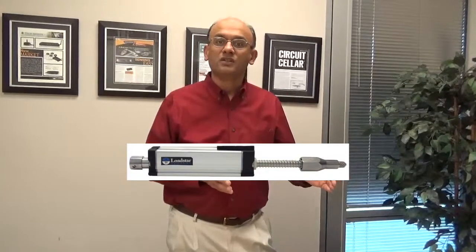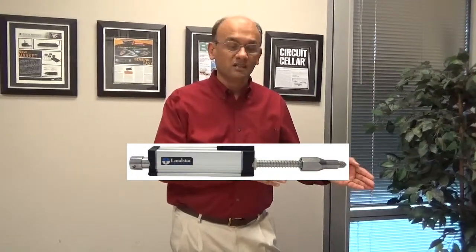I would say for about one or two inches I would recommend the LVDTs. For just thousandths of an inch, less than a quarter inch, I would recommend the Loadstar iDISC sensor. And then for much longer ranges I recommend the string pot solution.